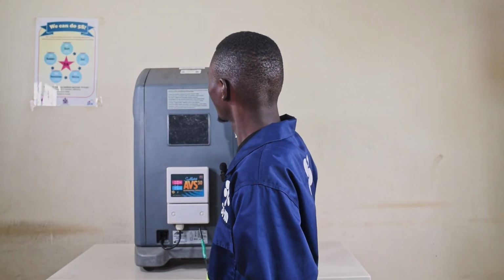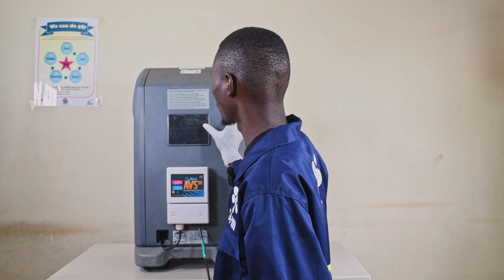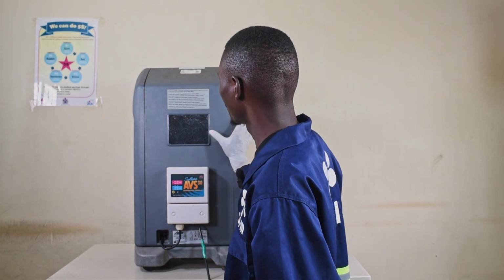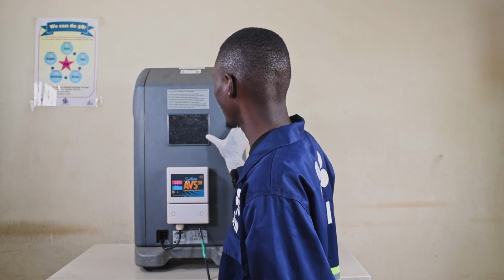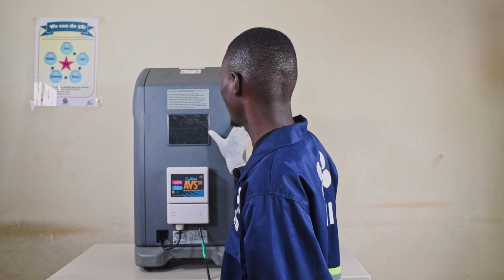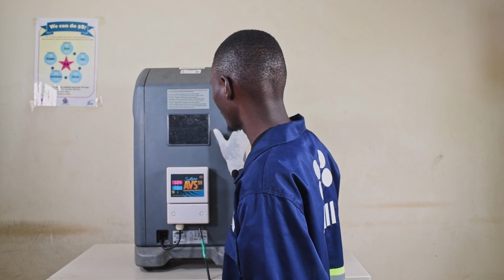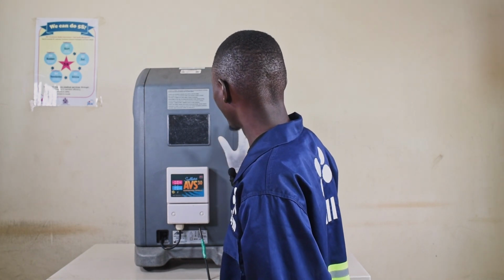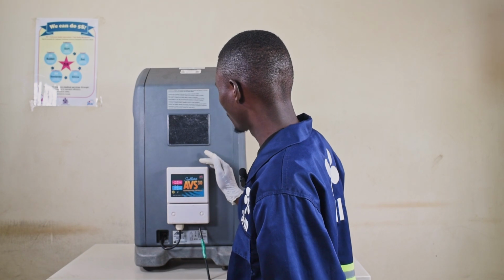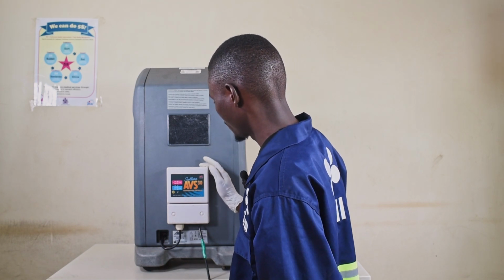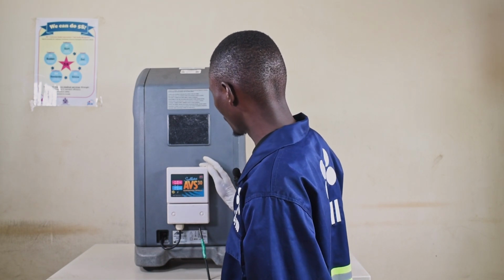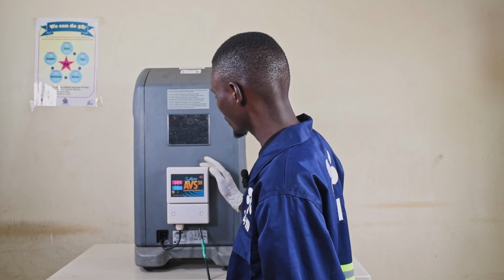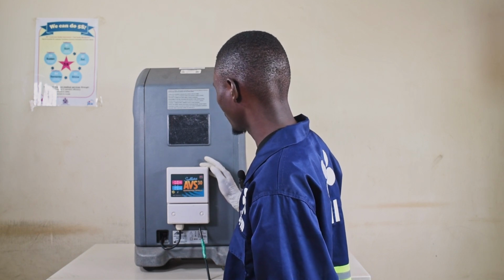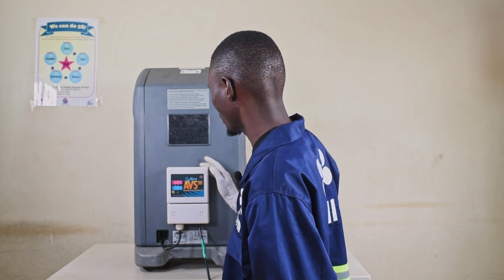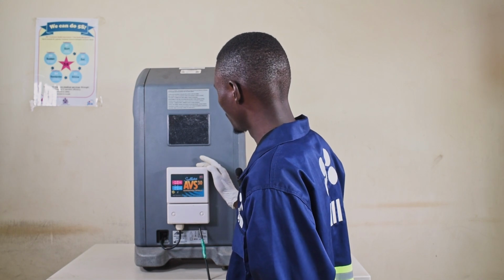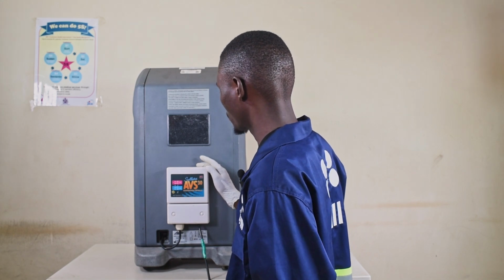On the back side of the machine, we have the gross particle filter. So this is used to remove dust and other large particles present in air before it enters the unit. And for this machine, an automatic voltage switcher has been connected. It switches off the machine once the mains power goes outside the preset acceptable limits. It automatically switches on the unit once the mains power returns to normal.